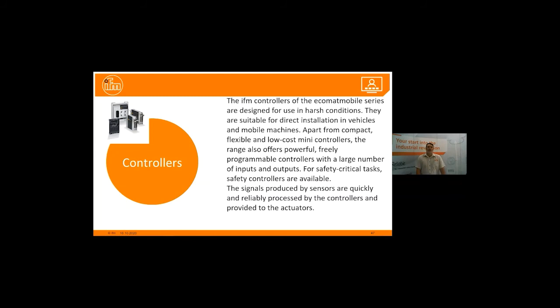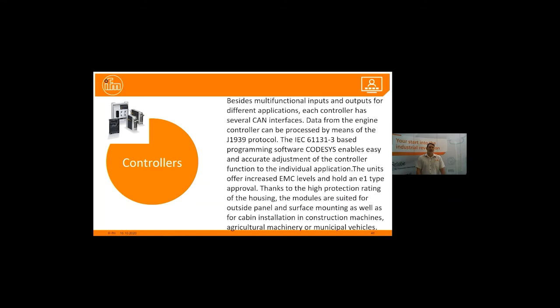The signals produced by the sensor are quickly and reliably processed by the controller and provided to the actuator. Besides multifunctional inputs and outputs for different applications, each controller has several CAN interfaces. Data from the engine controller can be processed by means of the J1939 protocol. The IEC 61131-3 based programming software CODESYS enables easy and accurate adjustment of the controller functions to the individual application. The units offer increased EMC levels and an E1 type approval.